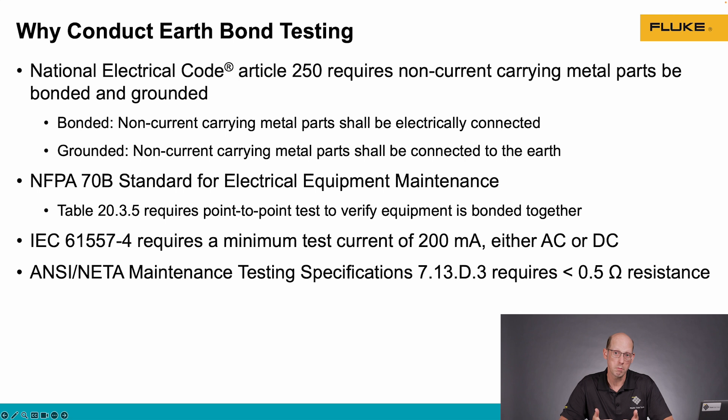The ANSI/NETA maintenance testing specifications 7.13.D.3 requires that when we do this test, the result is lower than half an ohm of resistance. So we want a really low resistance between our non-current carrying metal parts.